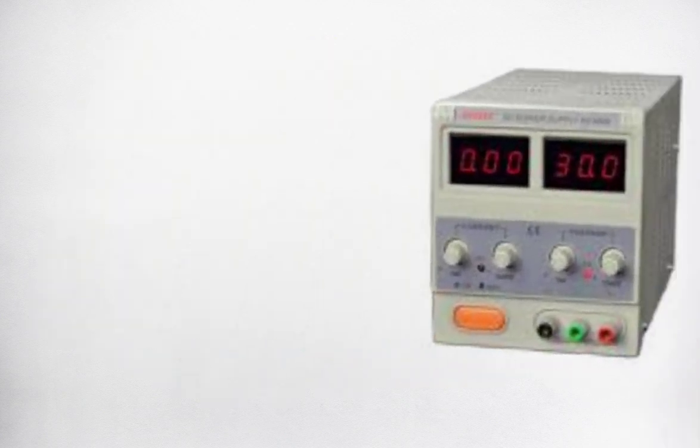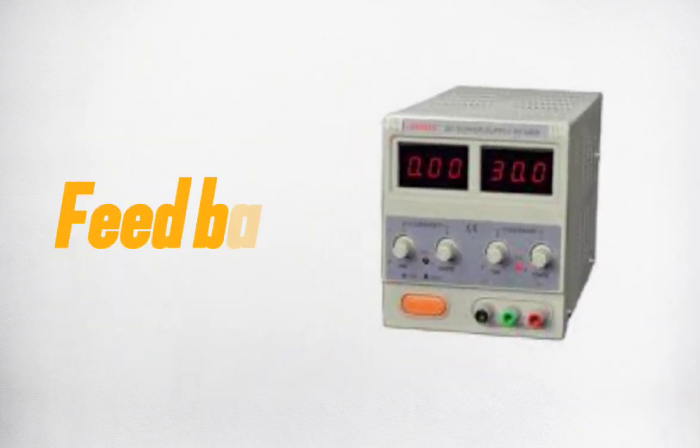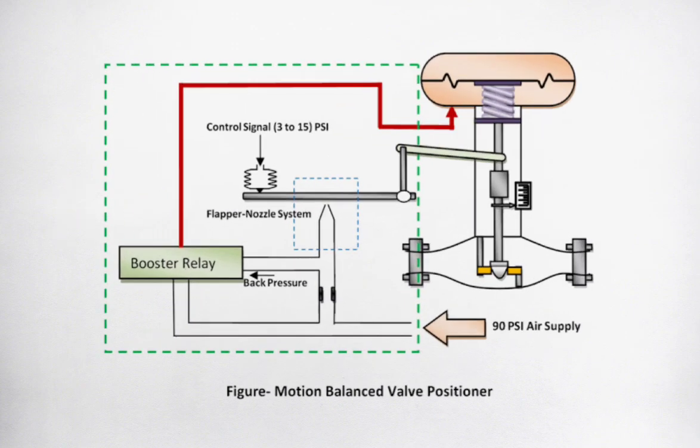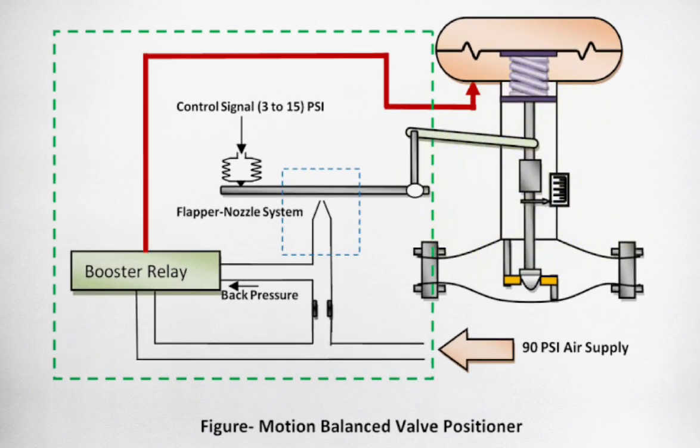Check the supply voltage. If the feedback to the valve positioner is through the mechanical link, check its condition. If the mechanical link is corroded, replace it. Also check other valve accessories: air volume booster, trip valve, quick exhaust valve, etc., if available.